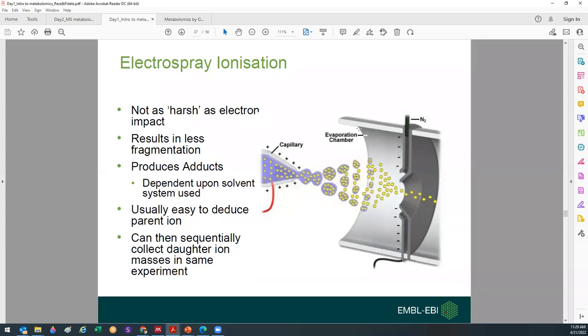In LC-MS metabolomics, one of the ionization methods mostly used is ESI — electrospray ionization. You have a capillary on which you apply high voltage, your samples come through in liquid form, and you apply a nebulizer gas to vaporize the solvent. As the droplet comes out from the capillary it is charged. With the gas, the solvent evaporates, the droplet becomes smaller, and due to Coulombic repulsion, it splits into smaller droplets until you are left with your analytes in the gas phase bearing a charge — protonated, deprotonated, or as adducts.